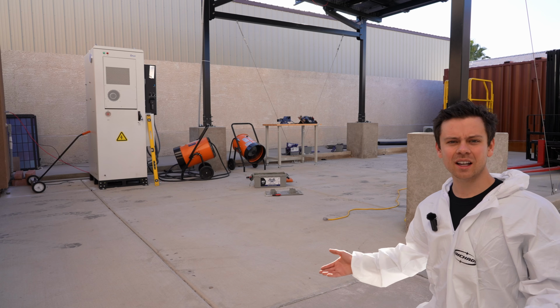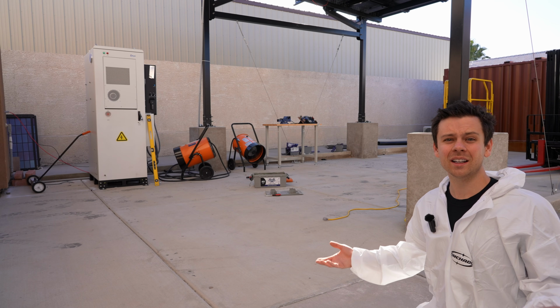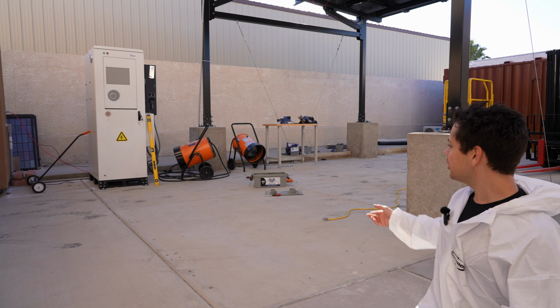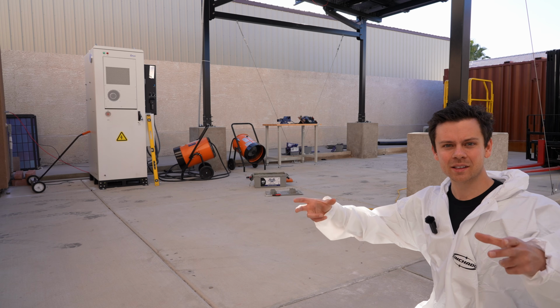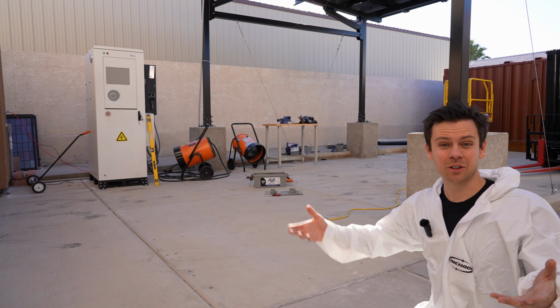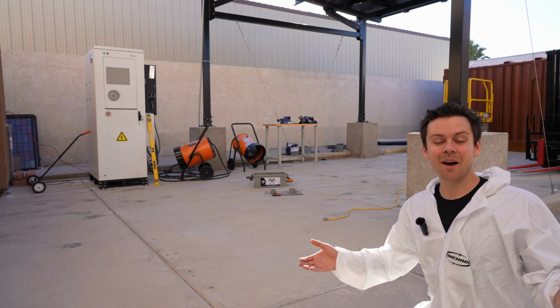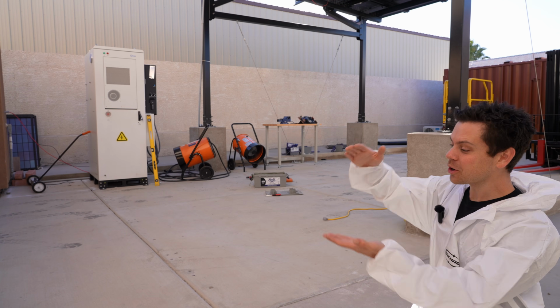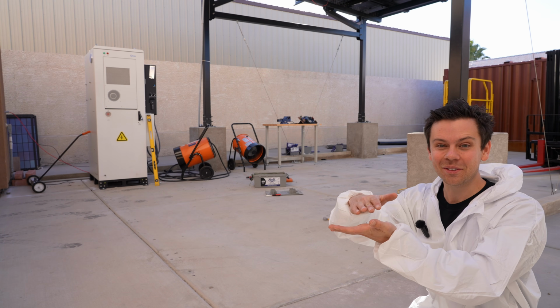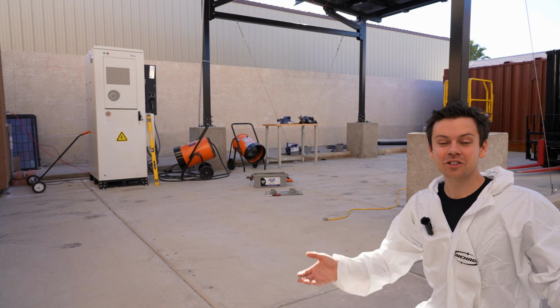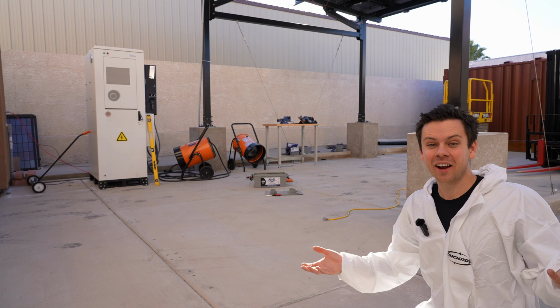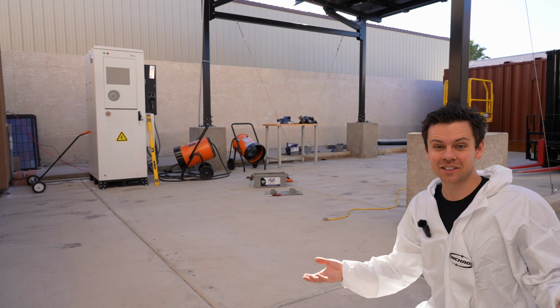To make one of these cells fail, you have to get them pretty hot and abuse them pretty hard. I noticed that when I lifted off the BMS, contact with the cells below was not made with a mechanical connection. There were just plates sitting on top of each other. That's it. If there's no mechanical connection, it will generate heat, and that can cause cells to fail.